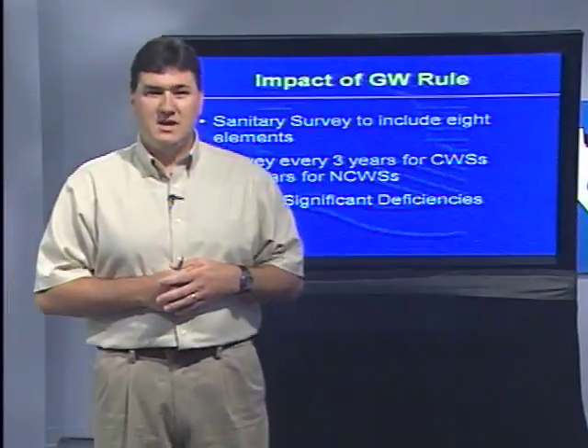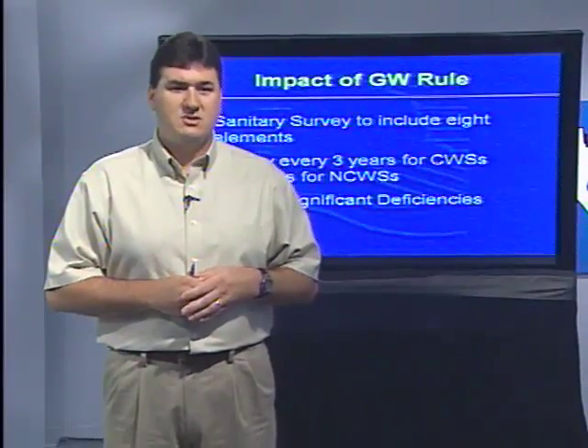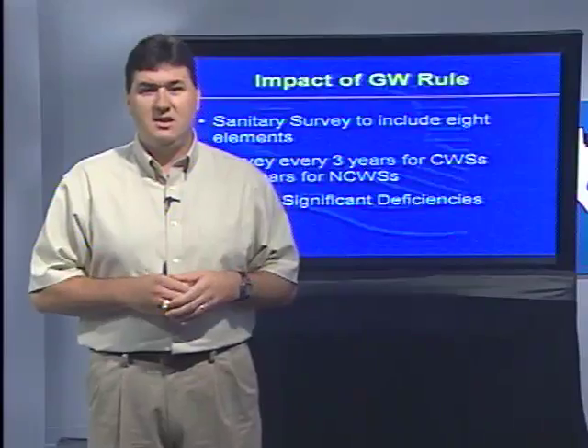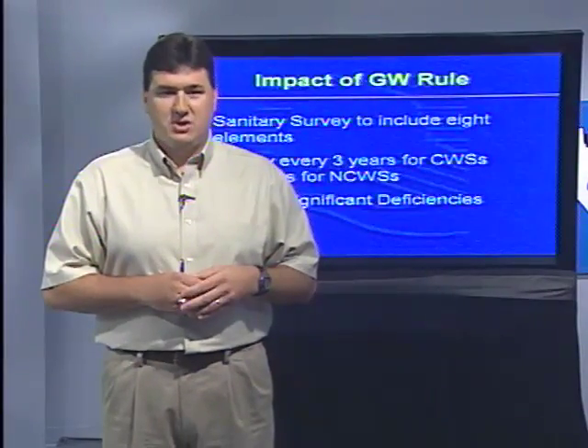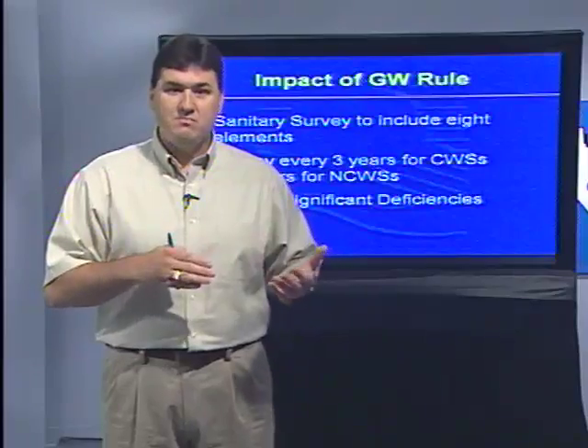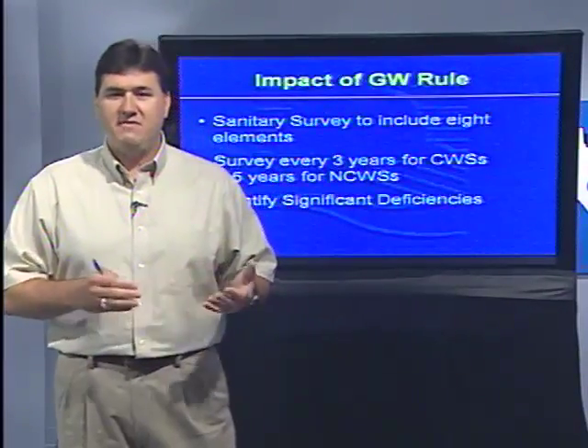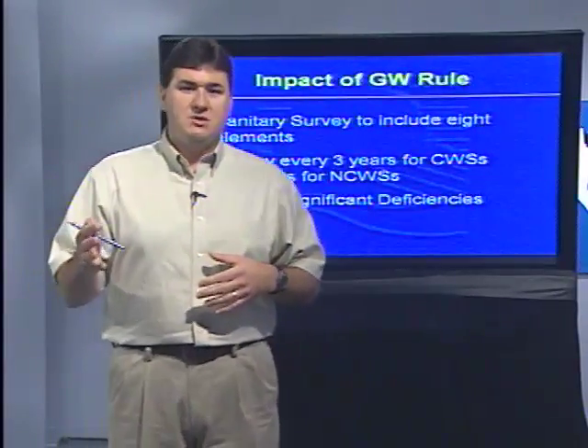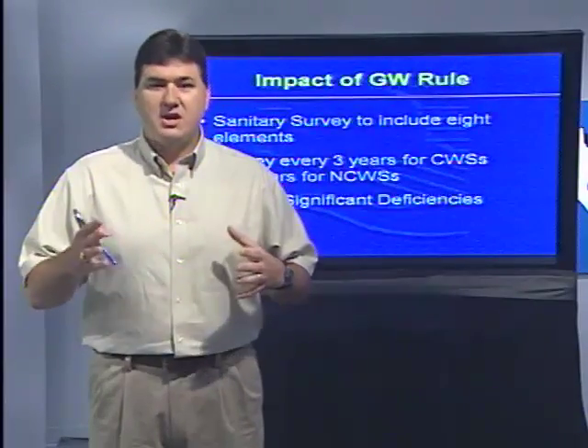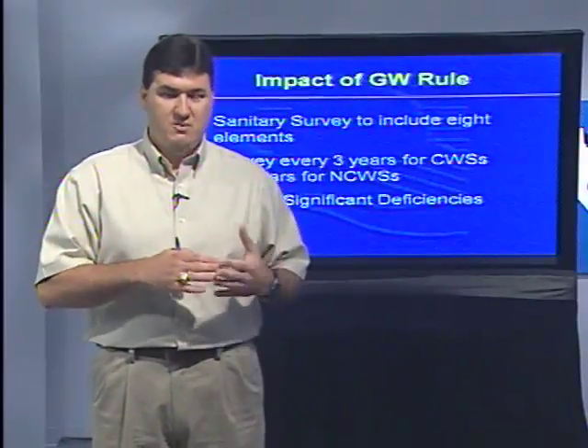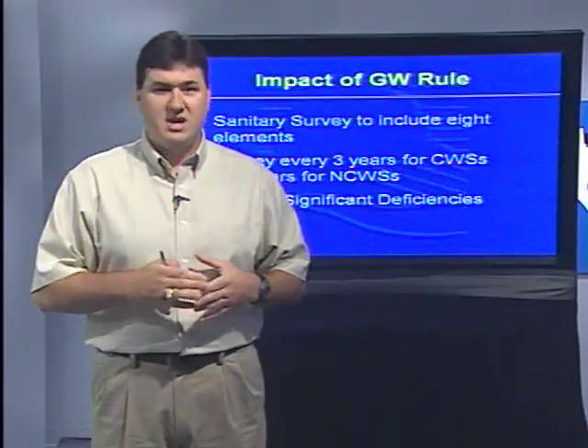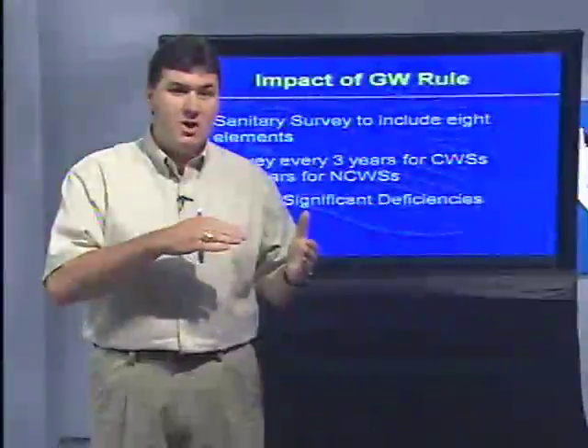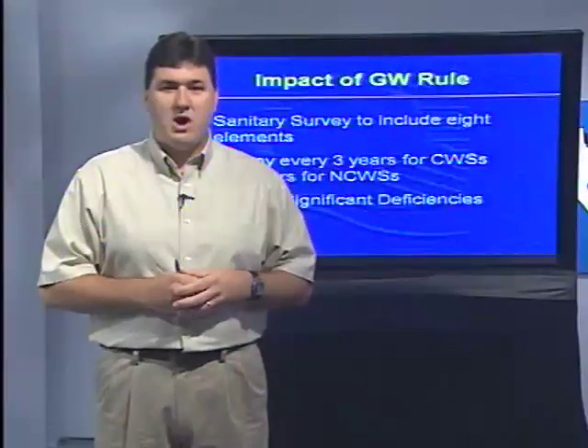Surveys have to be conducted every three years for community water systems and every five years for non-community water systems. This is the minimum frequency established in the groundwater rule. However, we may visit your site more frequently. We may also come out and conduct an investigation that's not a sanitary survey — a complaint investigation or a focus investigation. There are numerous investigations we may conduct, but for the groundwater rule the minimum requirement is three and five years.